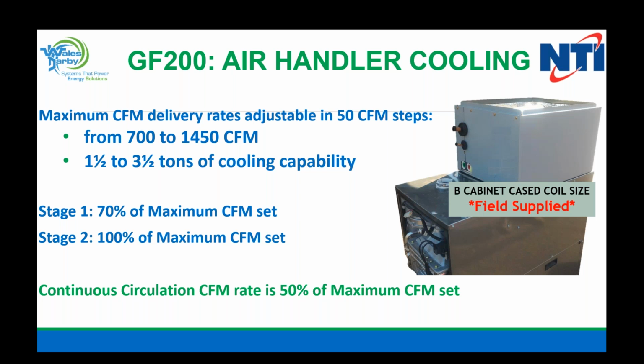A little bit different here on the cooling side. We have a maximum of 1450 CFM, and we range all the way down to 700. If we want to just have constant flow, you're looking at about 50% of the capacity. Every 50 CFM is a step. We'll show you that. Your capacity for cooling is 1.5 to 3.5 ton of cooling. And that's your stage breakout right there.